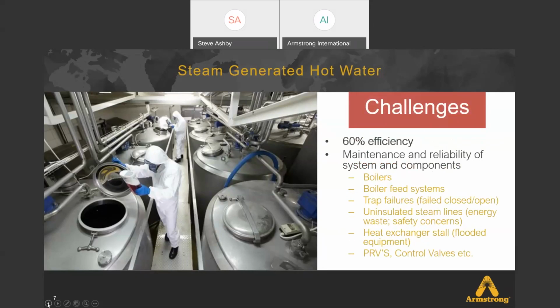The challenges with using steam, the main issue is the efficiency of it. Maintenance and reliability of the system and components is also challenging. It's maintenance intensive. You have your boilers, your boiler feed systems, your steam trap population. Uninsulated steam lines can be an issue, and quite commonly are in plants. Heat exchanger stall, where the equipment becomes flooded and impacts your critical temperatures for process. And just overall, parts and pieces in a steam system are pretty maintenance intensive.